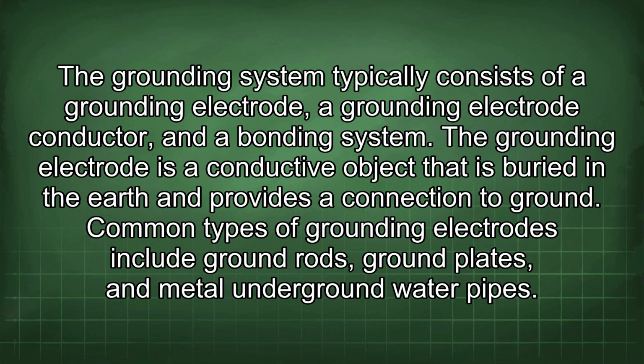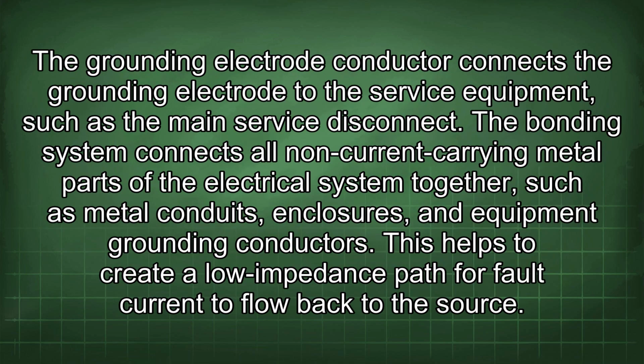The grounding system typically consists of a grounding electrode, a grounding electrode conductor, and a bonding system. The grounding electrode is a conductive object that is buried in the earth and provides a connection to ground. Common types of grounding electrodes include ground rods, ground plates, and metal underground water pipes. The grounding electrode conductor connects the grounding electrode to the service equipment, such as the main service disconnect. The bonding system connects all non-current carrying metal parts of the electrical system together, such as metal conduits, enclosures, and equipment grounding conductors. This helps to create a low impedance path for fault current to flow back to the source.